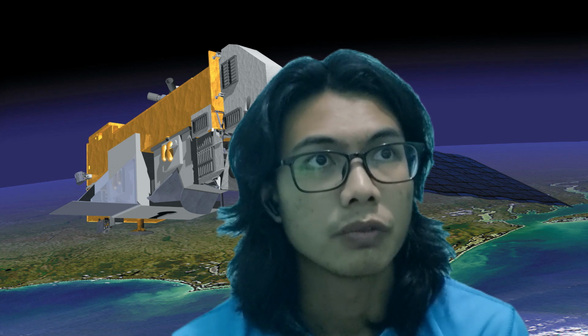Now, how is Fourier transform applied in the TES? Well, first, TES collects an interferogram, which is an analog signal representing the interference pattern created by the Michelson interferometer. This pattern results from the varying path lengths of the split infrared beams. Then the interferogram, which initially exists as an analog signal, is converted into a digital signal using an analog to digital converter (ADC). This conversion is necessary for the data to be processed by digital computers.